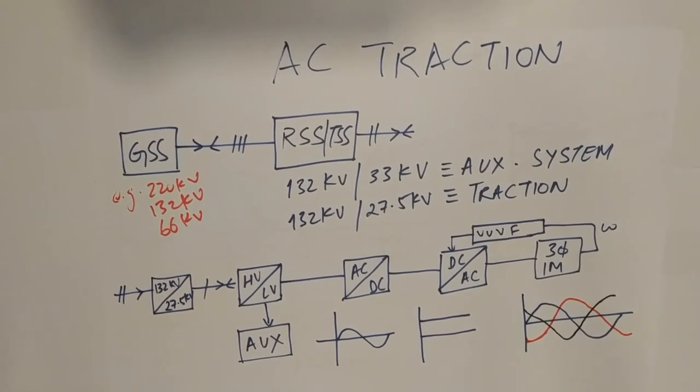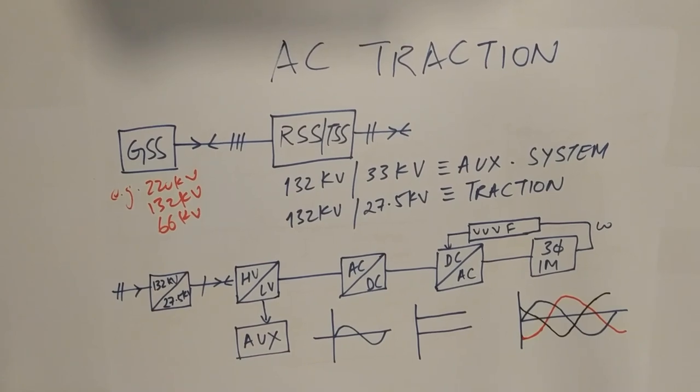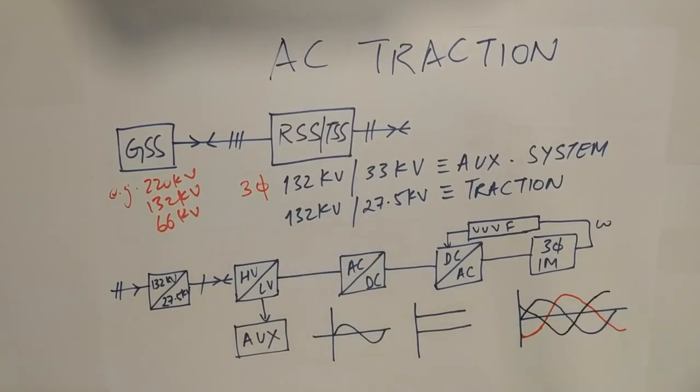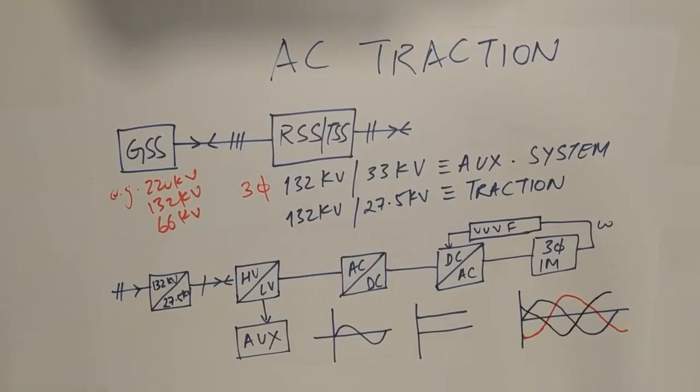For traction, 132 KV voltage is converted into 27.5 KV. Now, in this auxiliary, this is a three-phase voltage, a three-phase supply. Whereas, in traction, it is line-to-line. There is no third phase.